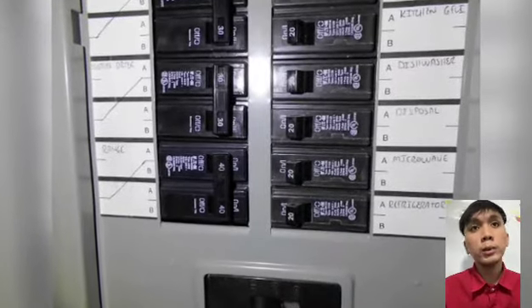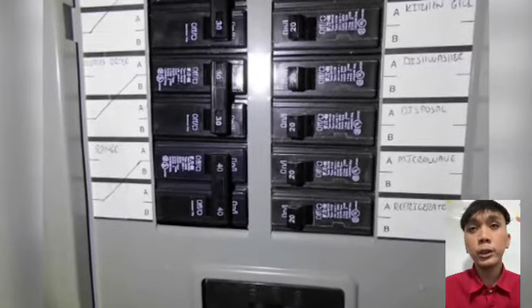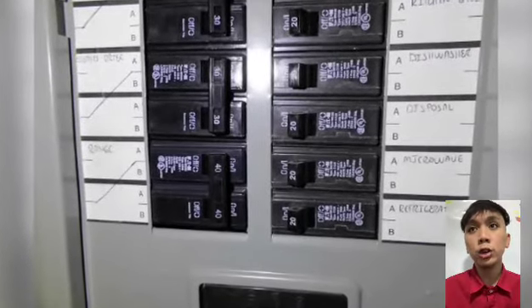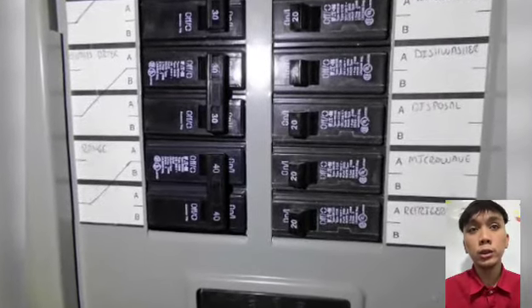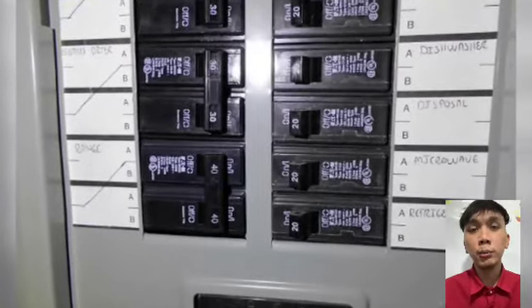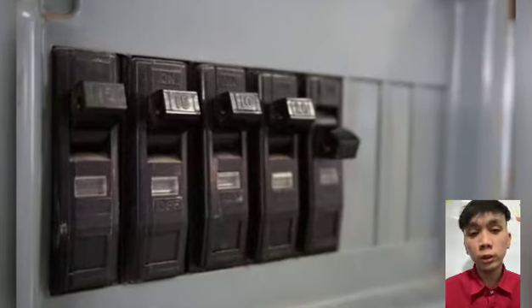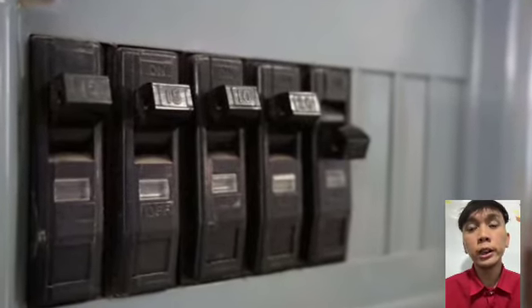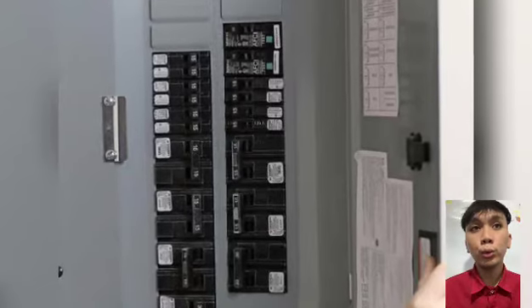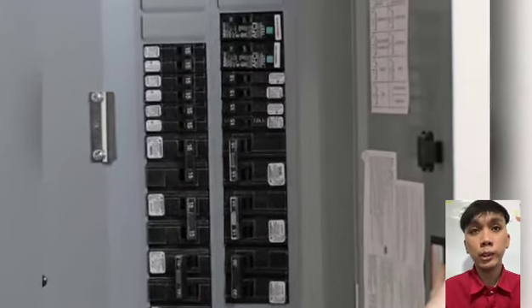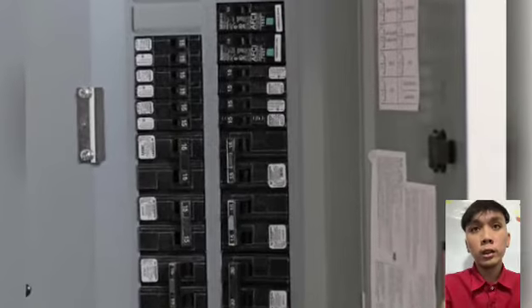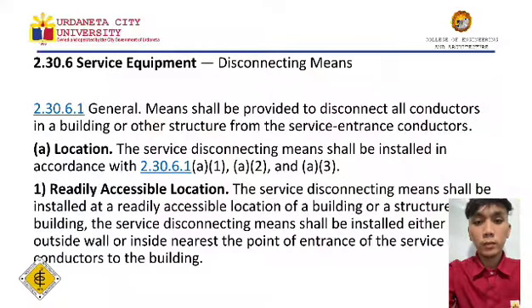The disconnecting means for each supply permitted by the code shall consist of not more than 6 switches or 6 circuit breakers mounted in a single enclosure. In a group of separate enclosures or on a switchboard or switchgear, there shall be no more than 6 disconnects per supply group in any one location.